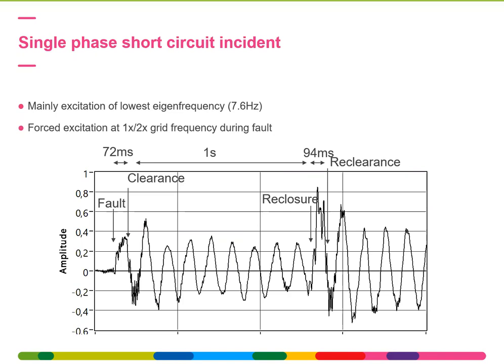In this event, the amplitudes were not dynamically magnified because the natural frequency is far enough away from once and twice grid frequency. So here, damage has not been done. There's not a lot of fatigue lifetime accumulation. So this event was assessed as not critical.